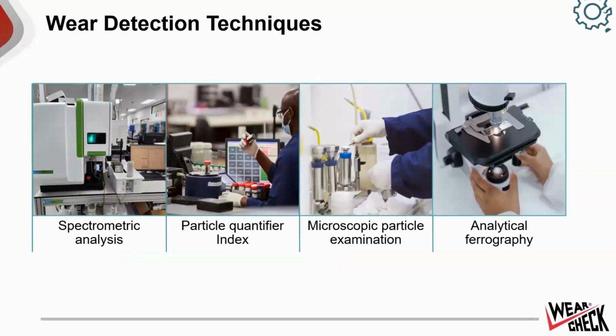So in terms of the techniques used to detect wear, these are probably the more common techniques that most commercial oil analysis laboratories would use. There's spectrometric analysis, which measures the concentration of elements associated with wear metals, contaminants, and additives in the oil. So these would be things like iron, copper, chromium, aluminium, calcium. The vast majority of spectrometers can measure anything from 30 to up to 40 different elements. And these are measured, as I've mentioned before, in parts per million.